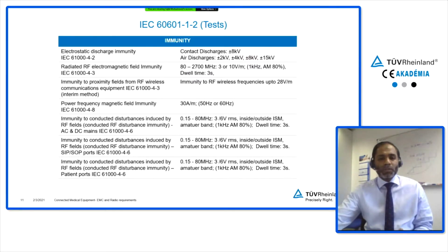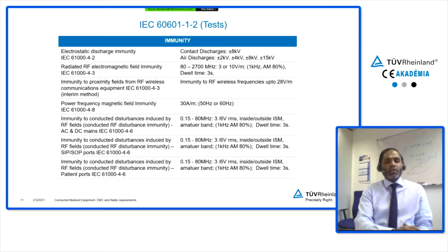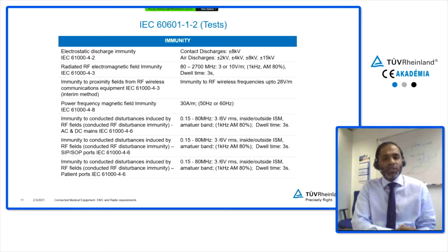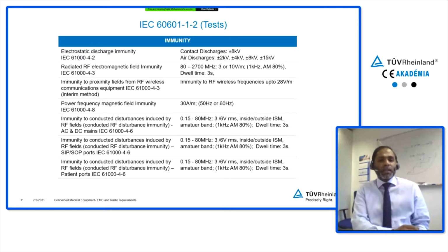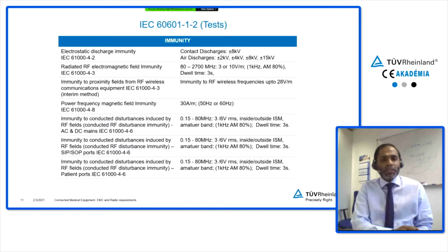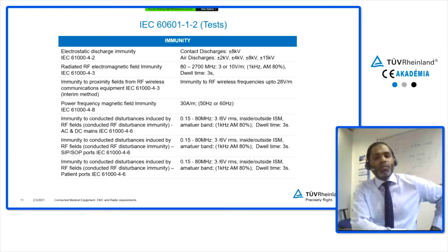The immunity part is again the standard electrostatic discharge immunity, IEC 61000-4-2. Contact discharges with plus or minus 8 kV, air discharges with plus or minus 2 kV all the way to plus or minus 15 kV. Radiated RF electromagnetic field immunity, IEC 61000-4-3, from 80 MHz to 2.7 GHz, either 3 or 10 volts per meter, with a dwell time of 3 seconds.